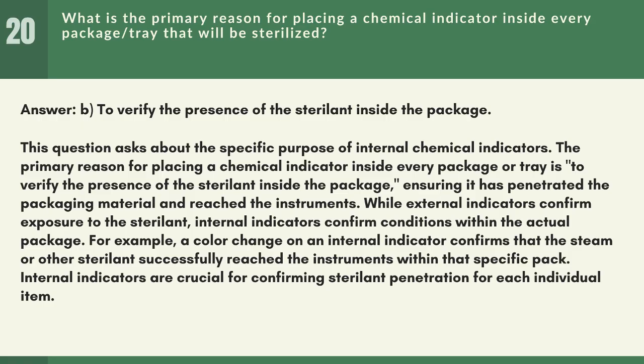While external indicators confirm exposure to the sterilant, internal indicators confirm conditions within the actual package. For example, a color change on an internal indicator confirms that the steam or other sterilant successfully reached the instruments within that specific pack. Internal indicators are crucial for confirming sterilant penetration for each individual item.